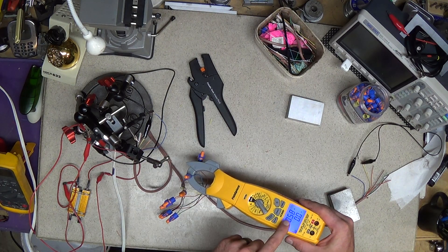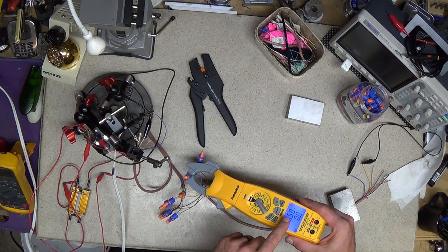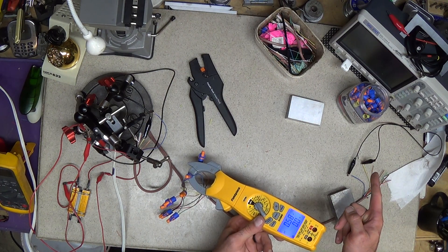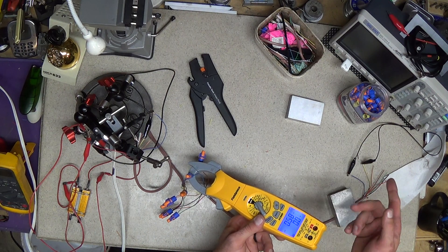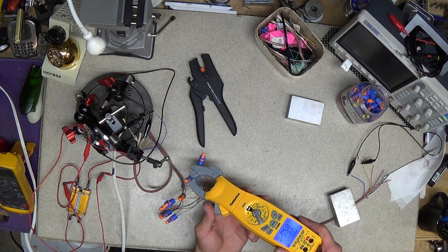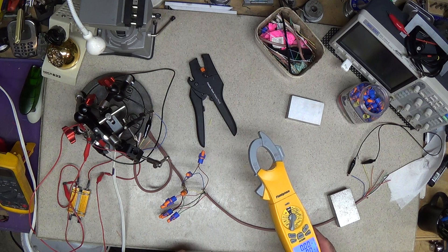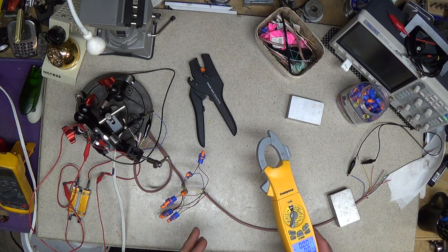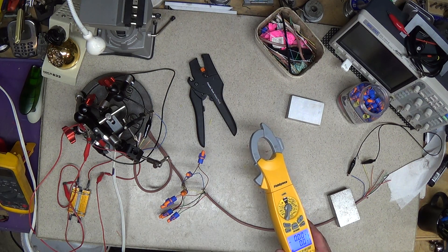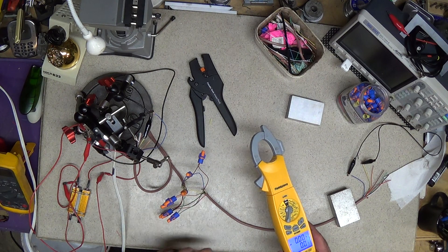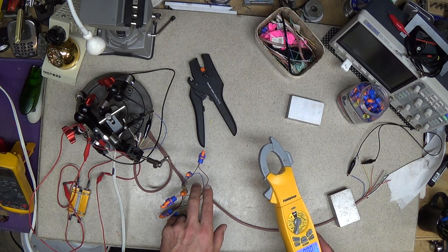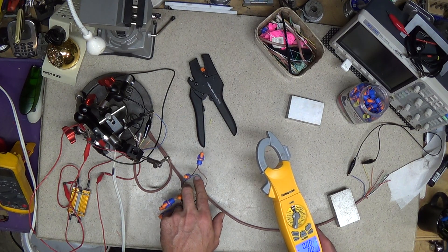So I do have also amperage on the common because my short is between yellow and common, so that makes sense. If the short was between yellow and say the case of the unit, I'm not going to have amperage on that common necessarily.